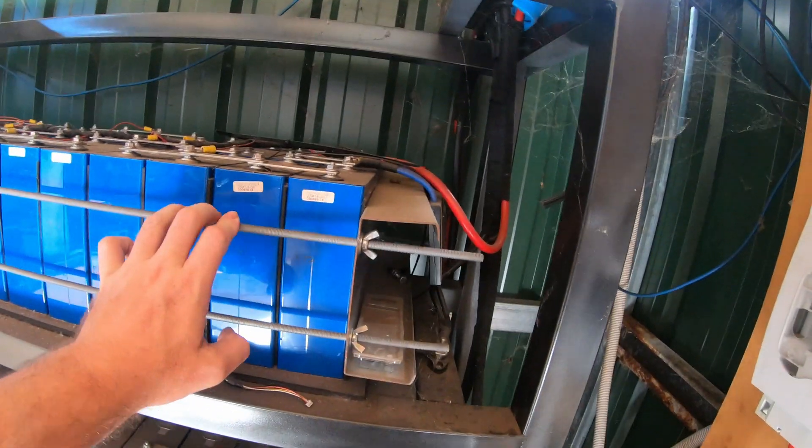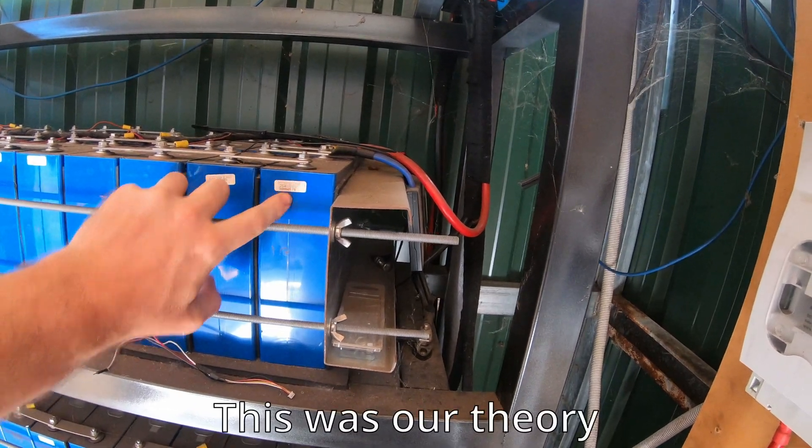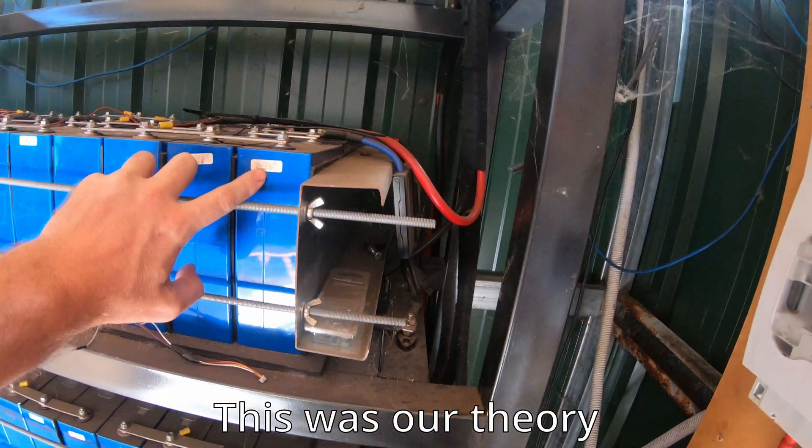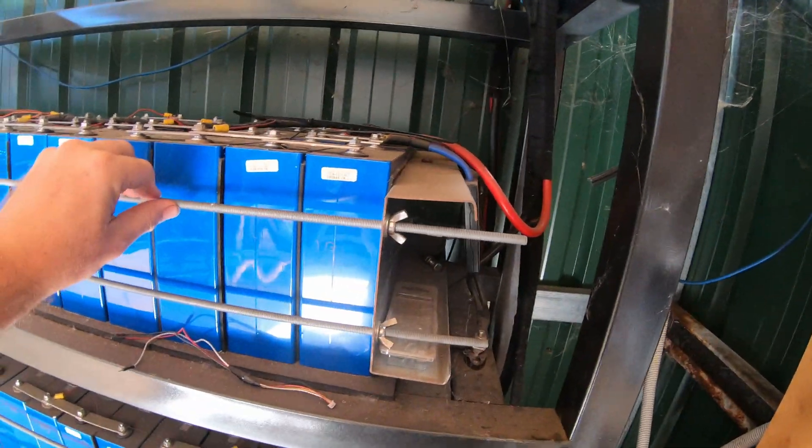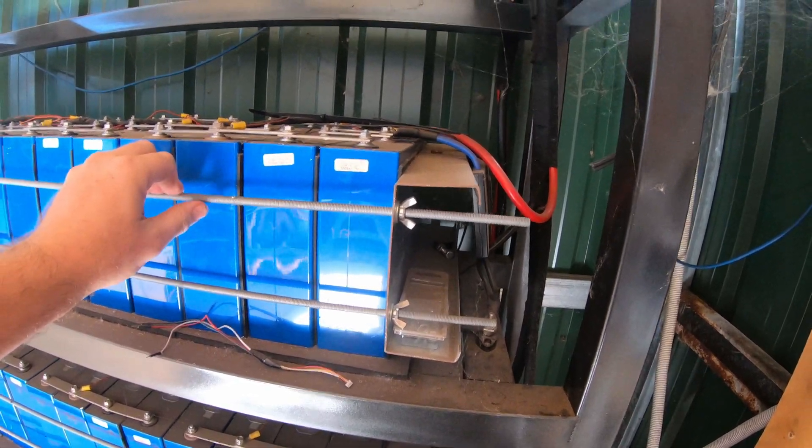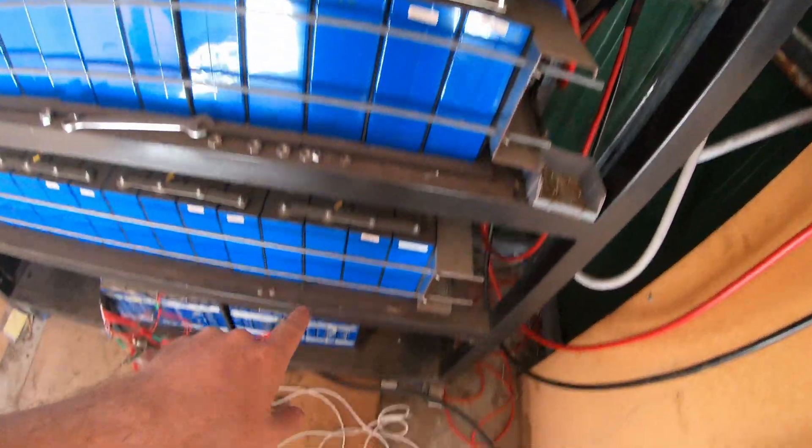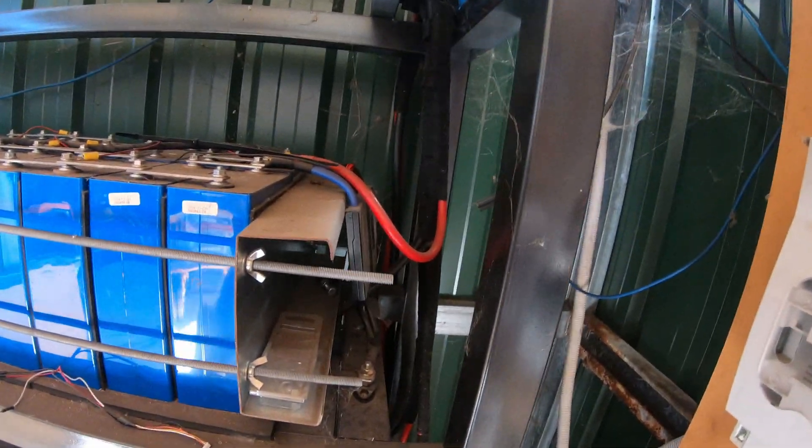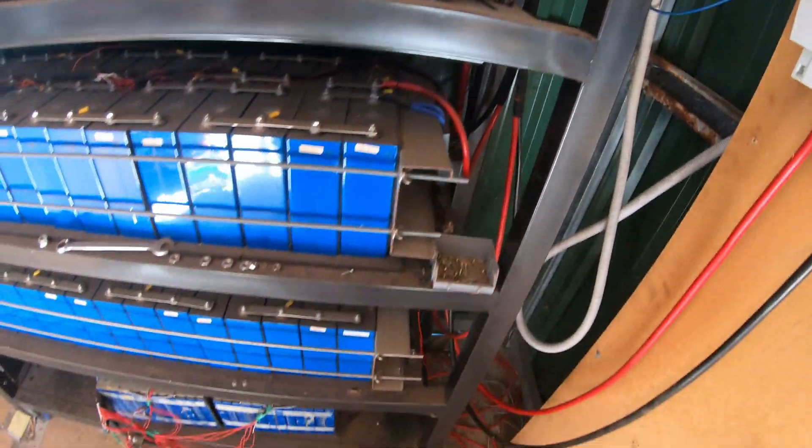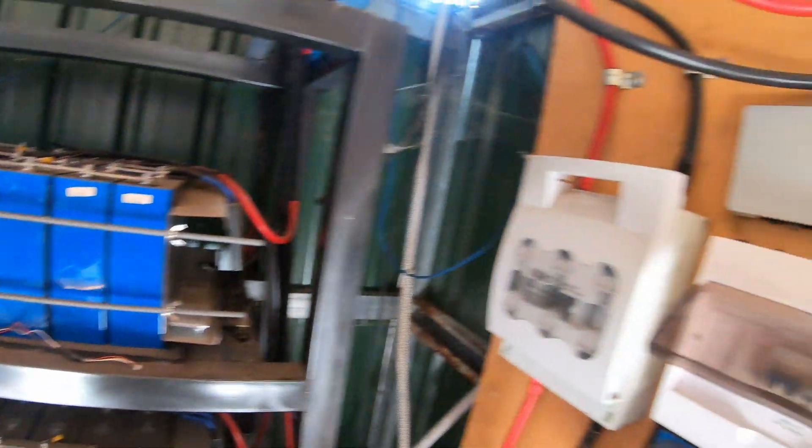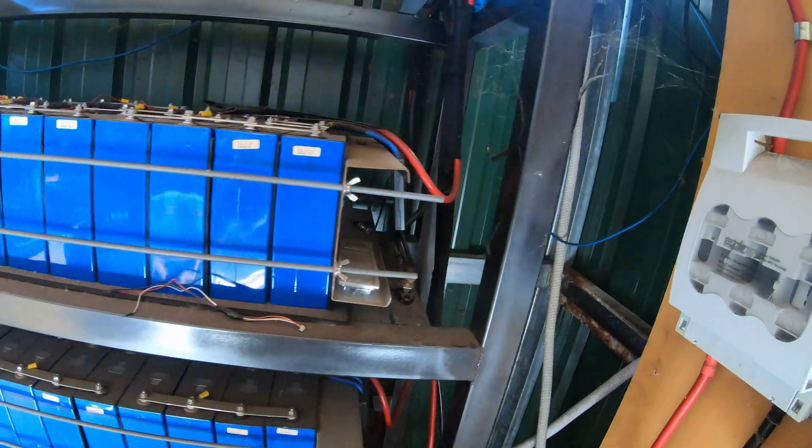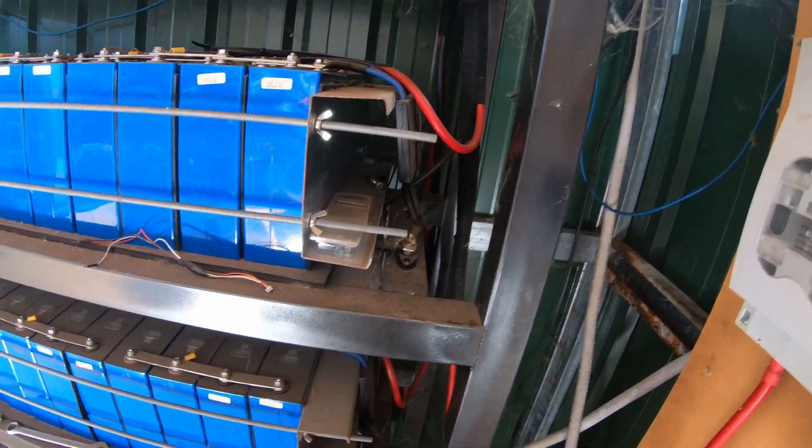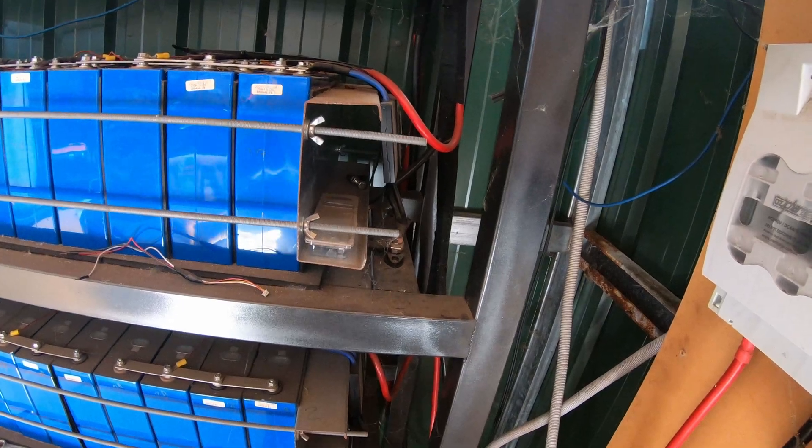Yeah, so that's where we're at. This top shelf appears to us to be - the shorter cable means that this one either discharges more and also gets more of the charge current. The only other thing could be is that that is actually the original shelf, and maybe there is something different about it. There's only a week difference between this one going in and this one going in - that one came in like two weeks later. So we always put it down to it's got to be the cable length, because we pretty consistently see that one is always at the highest state of charge, this one's always at the lowest. From the Victron's perspective this is all that matters - whatever voltage it sees is what's important. But otherwise, I come in here and I check the JK BMSs regularly.